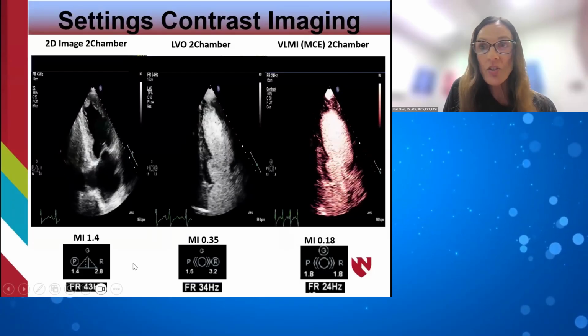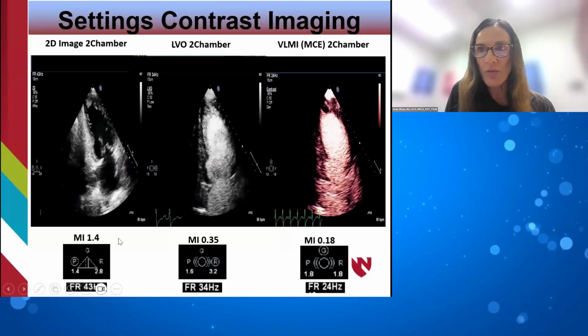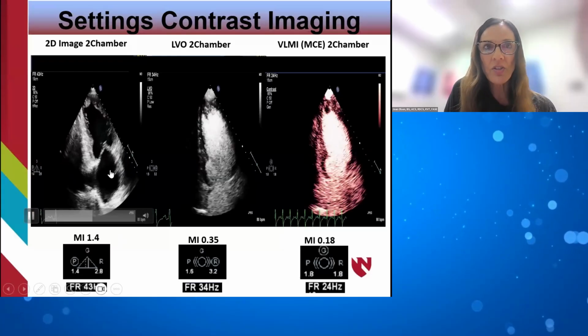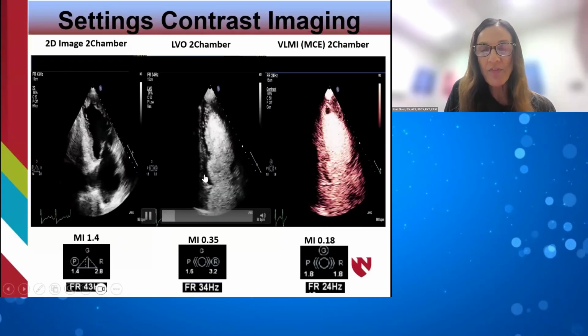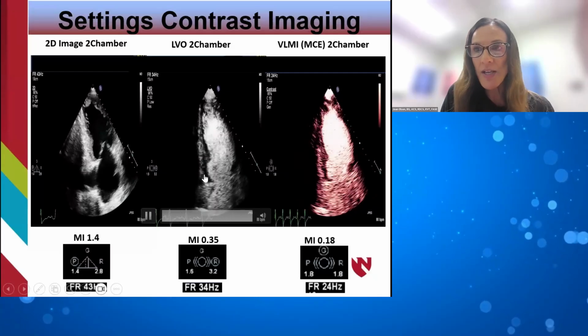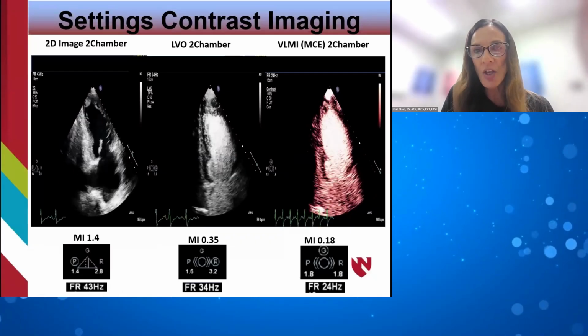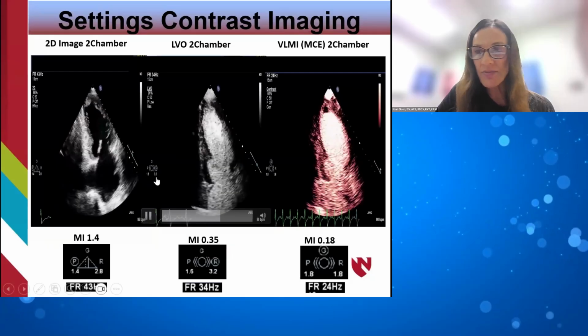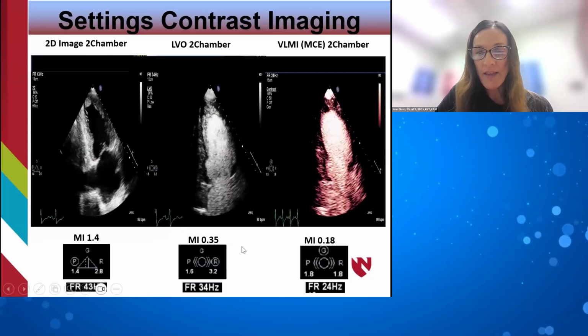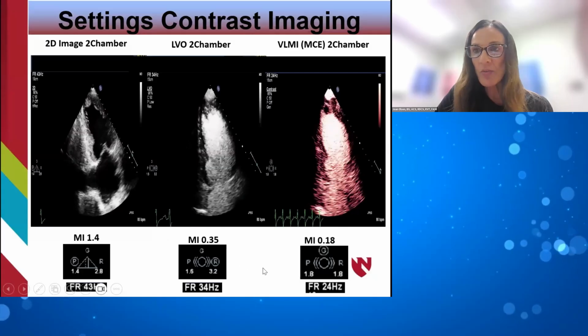So this is your conventional 2D imaging, and your MI with that is usually around 1.4. Take it one step further with your harmonic contrast imaging settings with your conventional LVO: you're sending and receiving at 2 different frequencies, and your MI then is around 0.35.